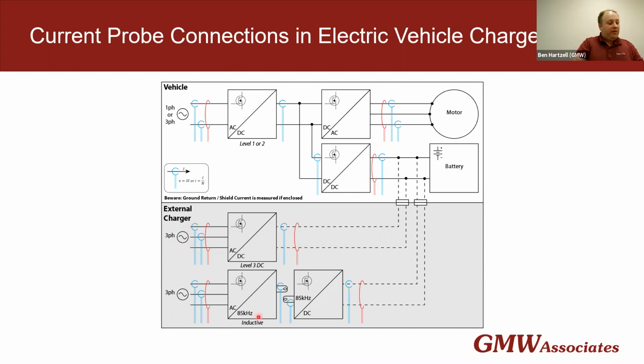The bottom of the lower half is again a similar input, but instead of AC to DC, we're talking AC to 85 kilohertz. And this would be for 85 kilohertz inductive charging. And here we would be measuring both the inductive transmit coil and the inductive receiving coil. And then again, after the 85 kilohertz DC inversion, we have some measurement points there.